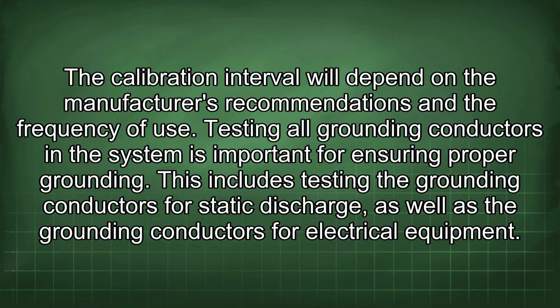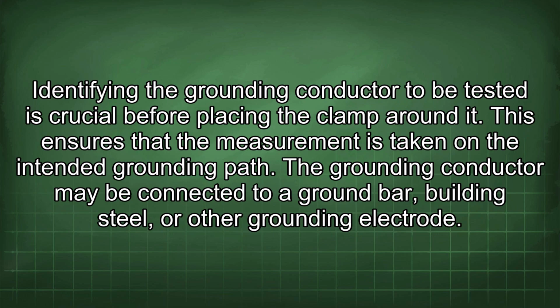Testing all grounding conductors in the system is important for ensuring proper grounding. This includes testing the grounding conductors for static discharge, as well as the grounding conductors for electrical equipment. Identifying the grounding conductor to be tested is crucial before placing the clamp around it. This ensures that the measurement is taken on the intended grounding path. The grounding conductor may be connected to a ground bar, building steel, or other grounding electrode.